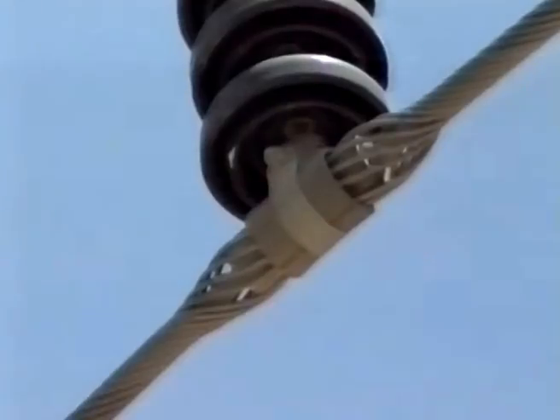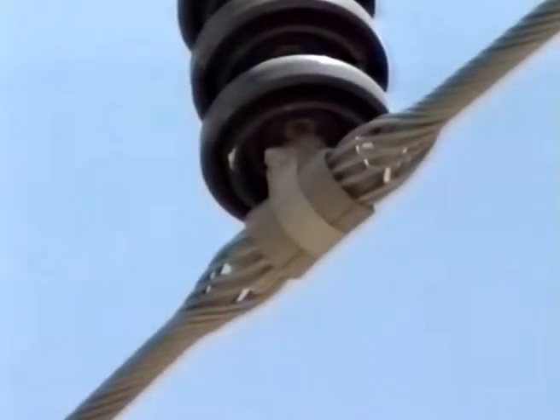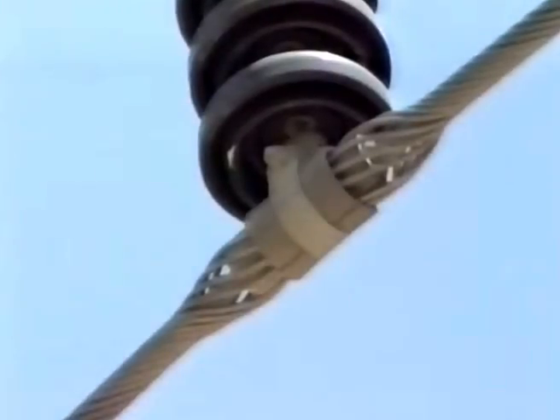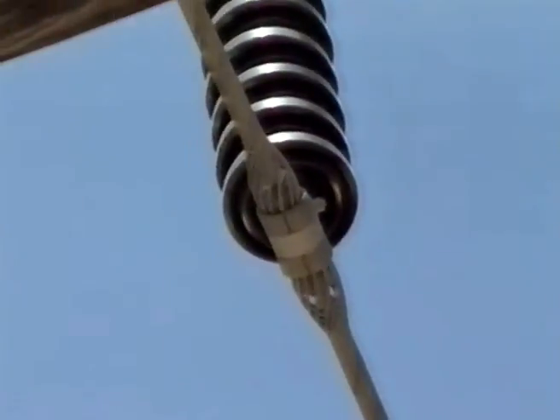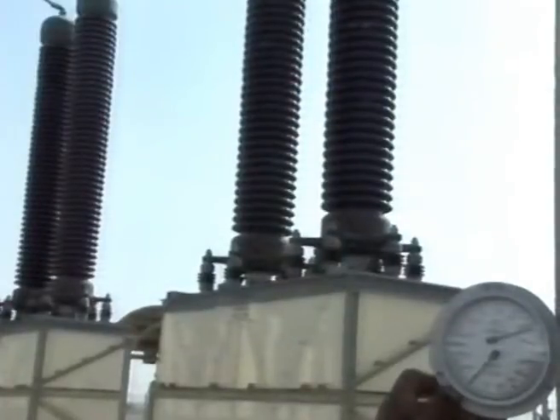Changing weather conditions greatly affect the performance of high-voltage insulators. Dust and high humidity contribute to the corona effect. There is a great tendency of flashovers when there is too much dust and humidity, lessening the insulating effect of insulators. This activity starts with the corona effect. It can only be seen at nighttime as in this footage.